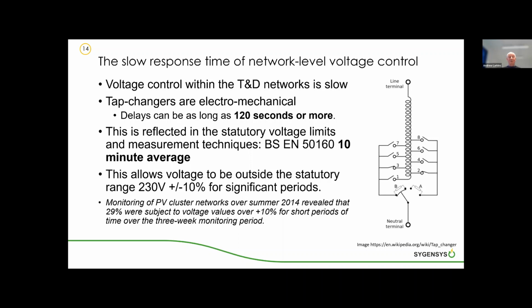Sample data from some PV has shown that 29% of sites were over plus 10% of the nominal voltage specification within just a 3-week monitoring period. So it's not that voltage excursions outside what we think of as the normal limits for short periods of time are uncommon.